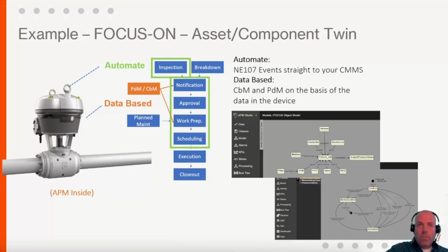So this digital twin, asset digital twin, allows companies to optimize their maintenance planning because the device itself runs models that indicate when maintenance activities, inspection, calibration activities are required. And it embeds our software to provide, for example, soft sensors for critical measurements that are being made on board, which are true digital twin representations of the actual measurements that can take over when measurements fail.